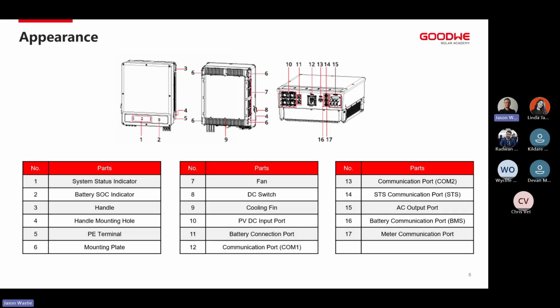This is just some of the parts and port numbers of the inverter itself. Most notably, you'll see port number 15. That is the AC output port. That is the only AC port on the inverter itself. And that's the port that we use if we're running this inverter as a grid-tied inverter for something like peak shaving or time of use application. We would use just that one port.